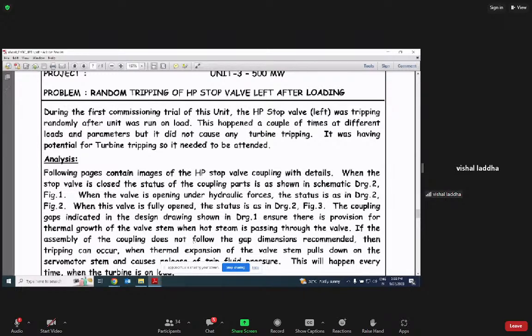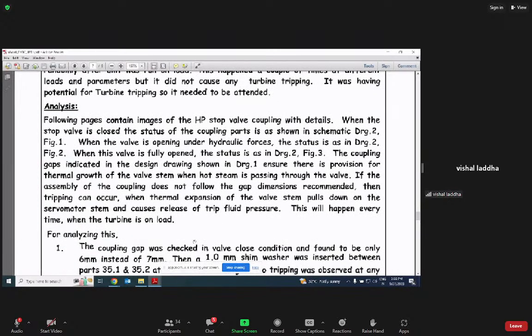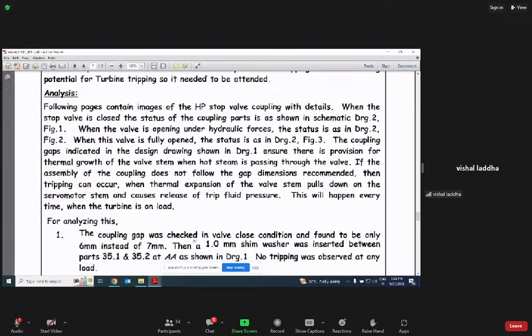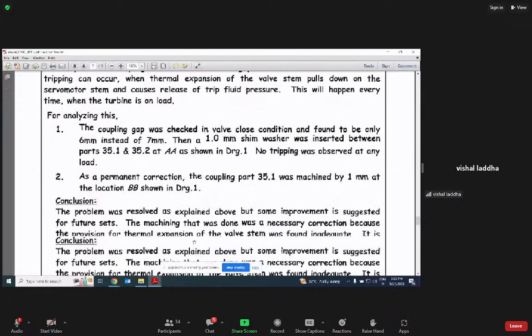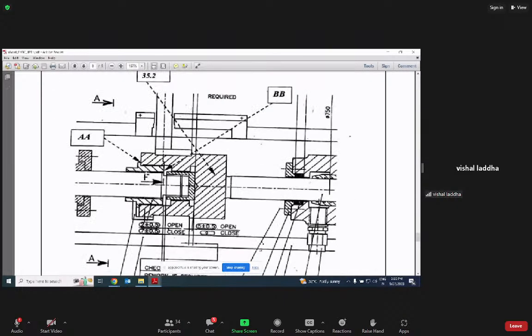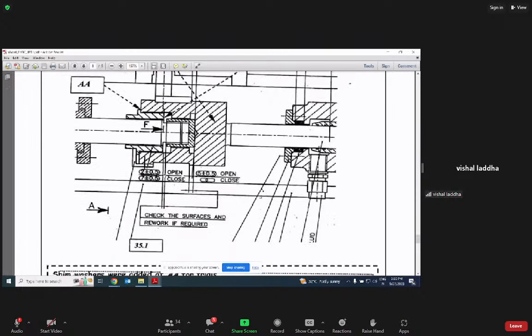The following pages contain images of the HP stop valve coupling with details. This is a purely mechanical situation. You check when the stop valve is closed; the status of the coupling parts is shown in schematic diagram 2. I will show diagram 1 and diagram 2. When the valve is opening under hydraulic forces, the status is in drawing 2, figure 2. When the valve is fully open, the status is like this, and when the valve is in the closed condition, it is as shown.